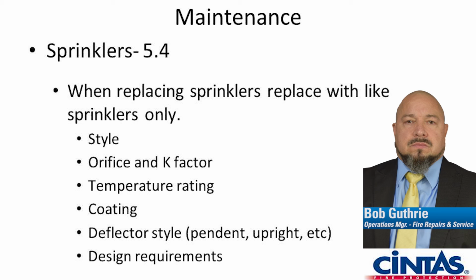You can have temperature ratings of sprinklers that are different. Say in a kitchen, right around the edge of the hood, we had a customer that was having problems. They were having false trips because we were reaching above 155 degrees for a very short period of time, but it was enough to discharge the sprinkler.